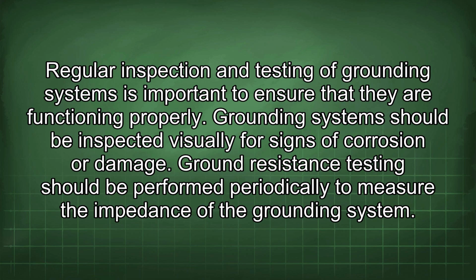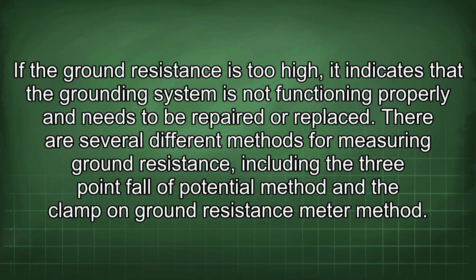Regular inspection and testing of grounding systems is important to ensure that they are functioning properly. Grounding systems should be inspected visually for signs of corrosion or damage. Ground resistance testing should be performed periodically to measure the impedance of the grounding system.